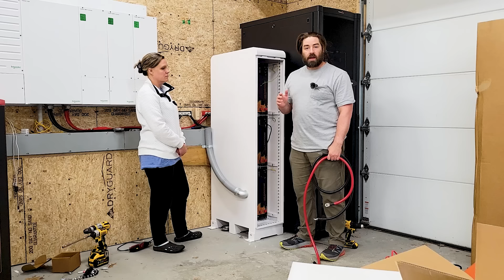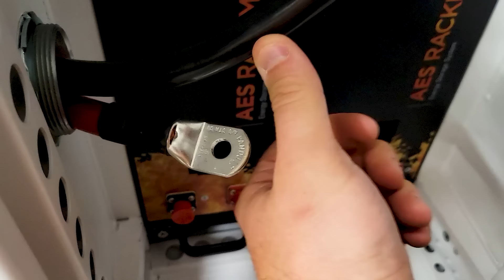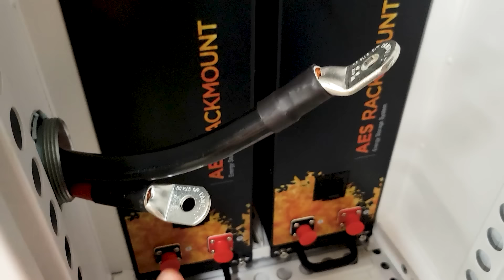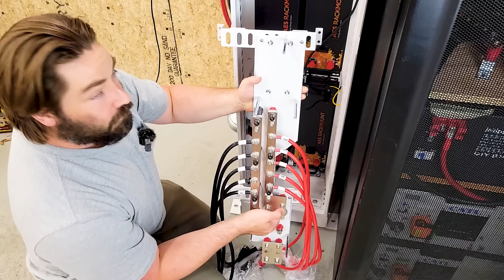I'm going to do 1 pair of the 4-aught - 1 negative, 1 positive - going through this 2-inch flex-tight conduit. It's a little tight when you already have the ring terminals crimped on the wires; it's easier if you do that after fishing them through the conduit. So let's get these through. The positive wire will come over to the circuit breakers and the negative up to the negative bus bar. Once we get the bus bars in place, we'll have to finagle them a little bit better.